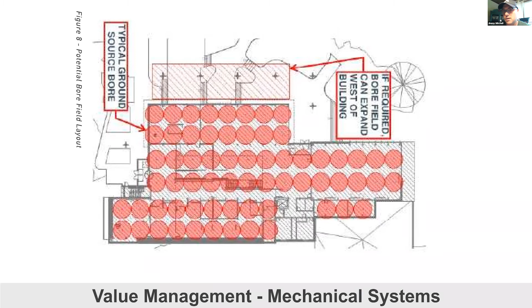The way the chillers work is they create chill water and discharge hot water. For us, that's when we use them in the wintertime. The discharge hot water, instead of going to a normal cooling tower system, actually goes through our floors to heat them. So in the wintertime, we're actually sending chilled water back to the chill water plant, giving it energy. This saved about $600,000 by tying into the campus chill water loop instead of doing the geothermal wells. Honestly, we got a great price on the geothermal wells, and if that loop hadn't been so close and convenient, I think it would have won out. But in this case, we ran it through that.